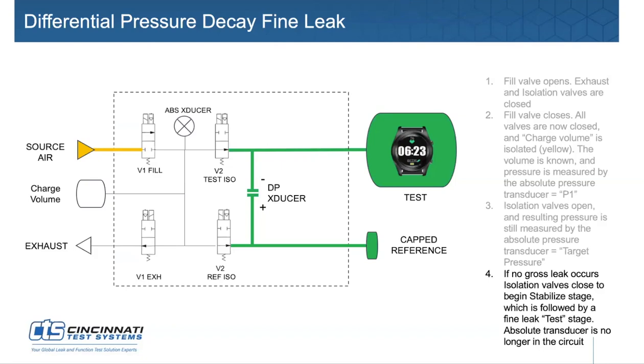That transducer's ranged in the typically 2 or 5 psi range. So if you're testing at 100 psi, your fill pressure transducer is going to be a 200 psi transducer, and you've now increased the amount of resolution going into the A to D converter for that DP transducer at 5 psi.